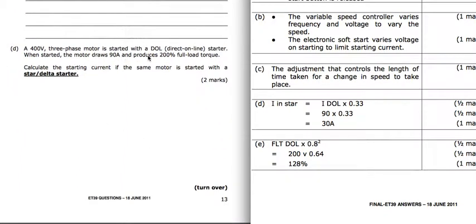D, a 400 volt three-phase motor has got DOL. When started, the motor draws 90 amps and produces 200% full load torque. So 90 amps on a DOL. Calculate the starting current if the same motor is started with a star delta starter. So when it's by a DOL, it's as if it's starting in delta. When we start it in star, the current that it takes is a third of the DOL current. So this 90 amps would be reduced by a third if we were able to start it in star. And so here we've got I in star is the I in DOL times 0.33, which is the third. So 90 times 0.33 gives us 30 amps.